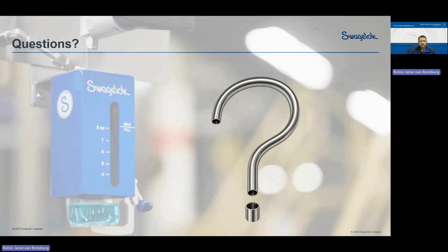Okay, so the only way to do that is to nitrogen purge your cylinder before you take the sample, so that you know there's nothing in that cylinder. What we've seen customers do is have a purging station that looks similar to the panel. In the lab, when they finish taking the measurements, they just plug it in and blow the whole cylinder clean with nitrogen for a minute or so, and then they install it.